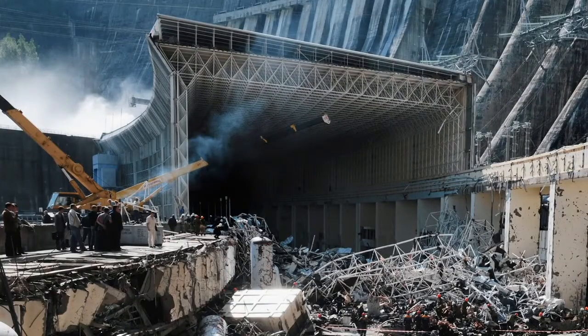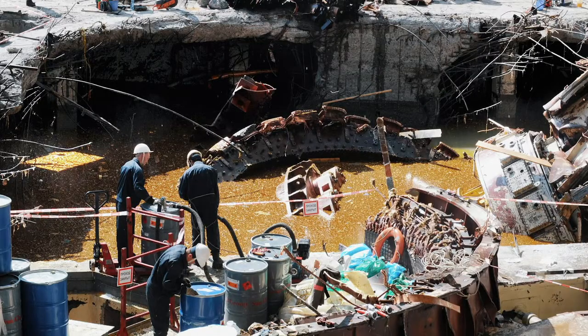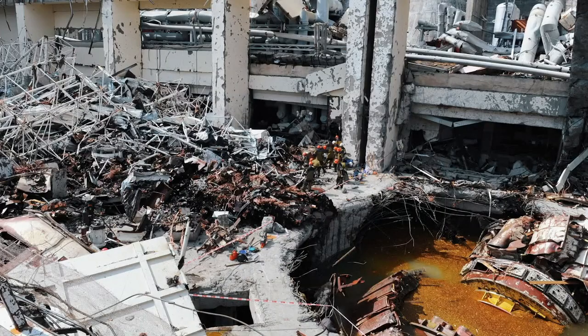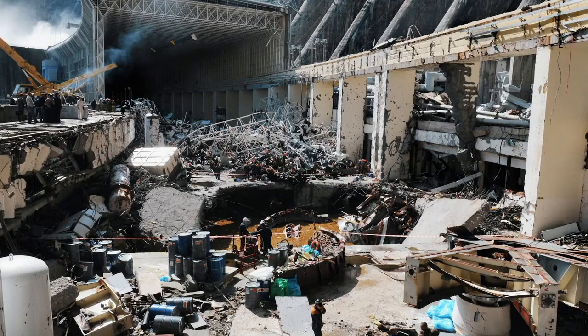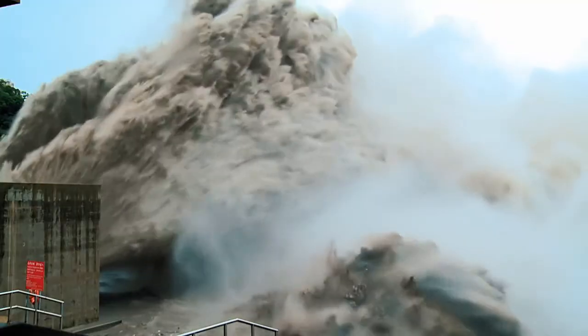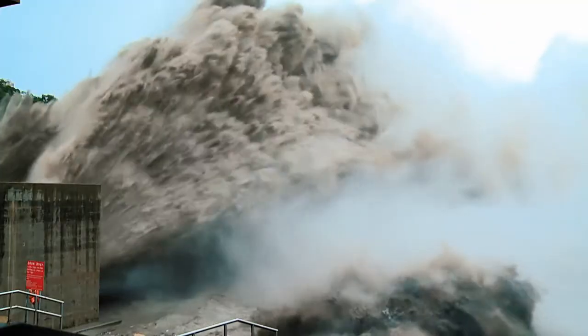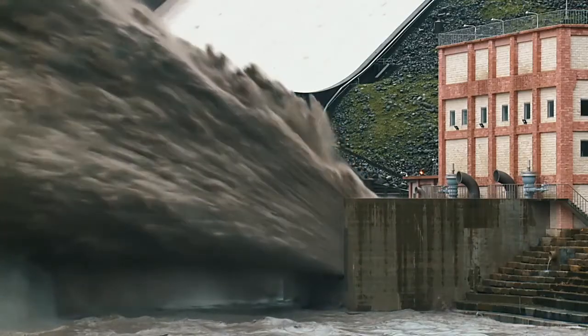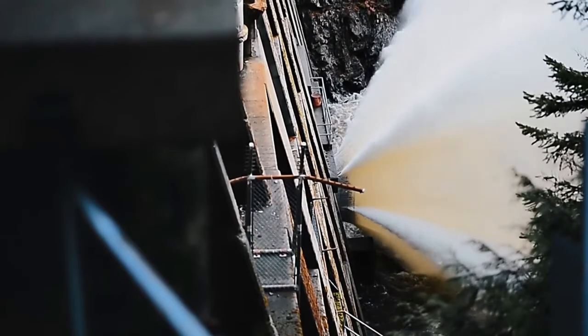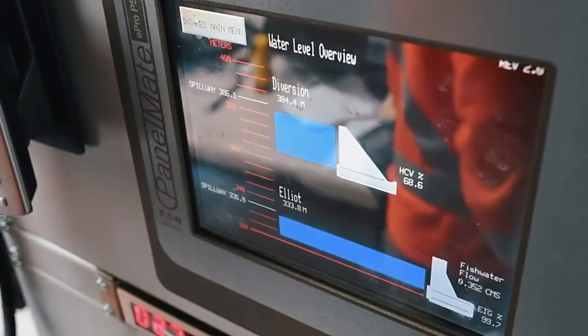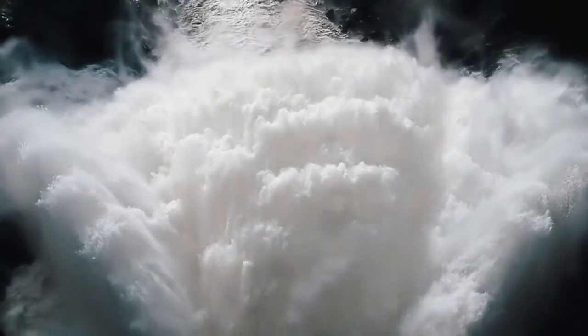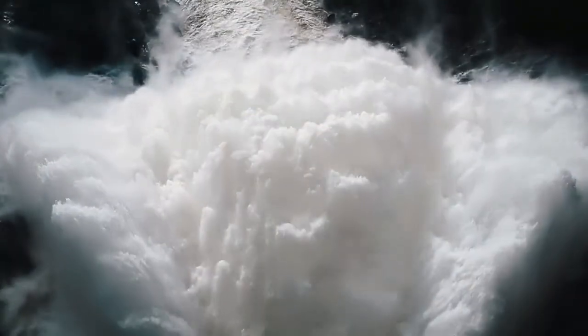The enormous weight destroyed the building itself and caused massive structural damage. The water instantly inundated the turbine hall, rushing in at a speed of 67,600 gallons per second. Equipment engineers immediately turned their attention to the Unit 2 wicket gates, but the incoming water began to short out electrical systems. They struggled to shut the gates because of the incoming water, and then lost electrical power and were unable to shut the turbines down.